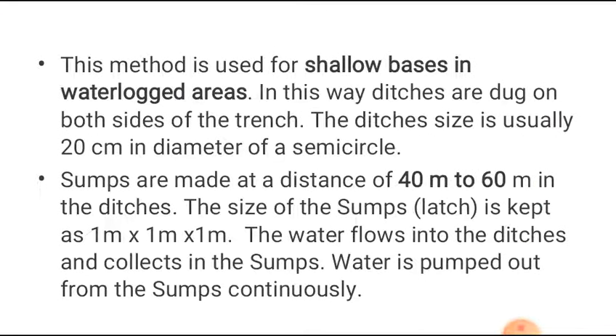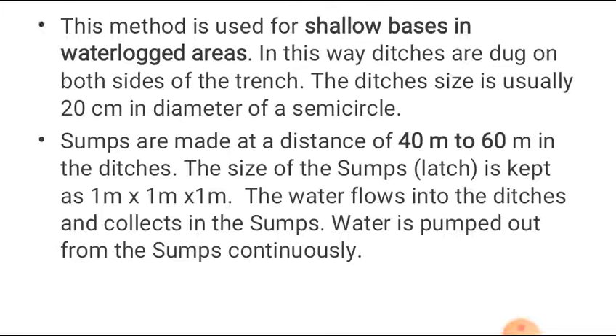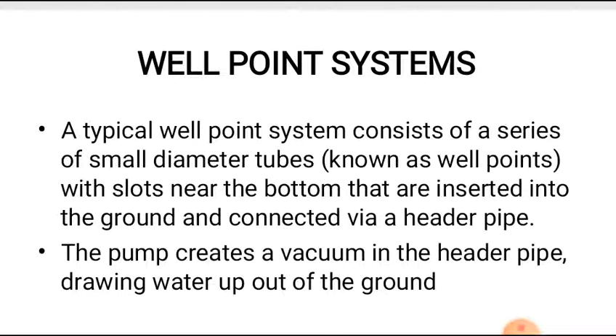This method is used for shallow bases in waterlogged areas. Ditches are dug on both sides of the trench. The ditch size is usually 20 centimeters in diameter of a semicircle, and sumps are made at a distance of 40 to 60 meters in the ditches. The size of the sump is kept as 1 meter × 1 meter × 1 meter. Water flows into the ditches and collects in the sump, then water is pumped out from the sump continuously.